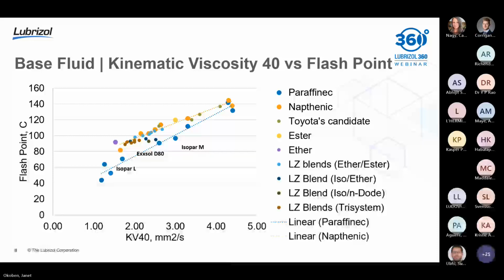Now, that sounds like we just want to move towards the lowest viscosity fluid that we can find. But we need to keep in mind that there's other things to be considered, such as material compatibility as well as safety. So viscosity and flash point of a fluid typically trend in the same direction. So those are very much directly correlated. The lower the viscosity of your fluid typically means the lower the molecular weight of the individual constituents, which means the higher volatility, which means a lower flash point.